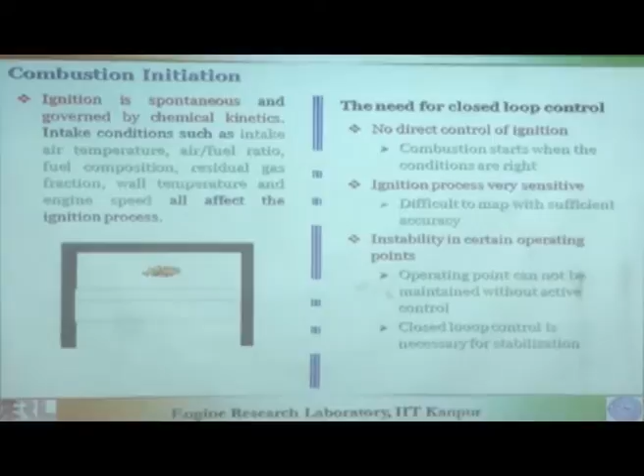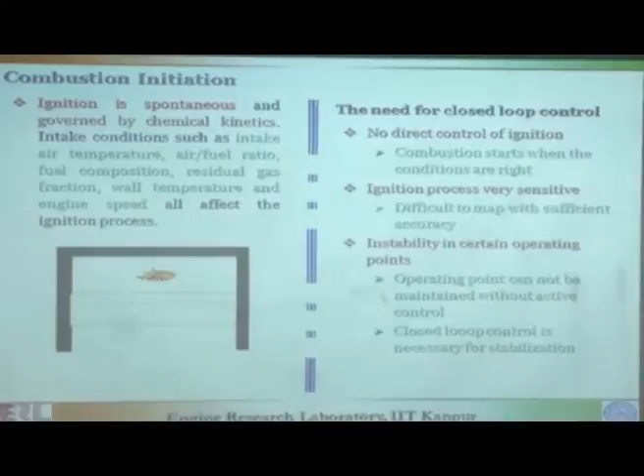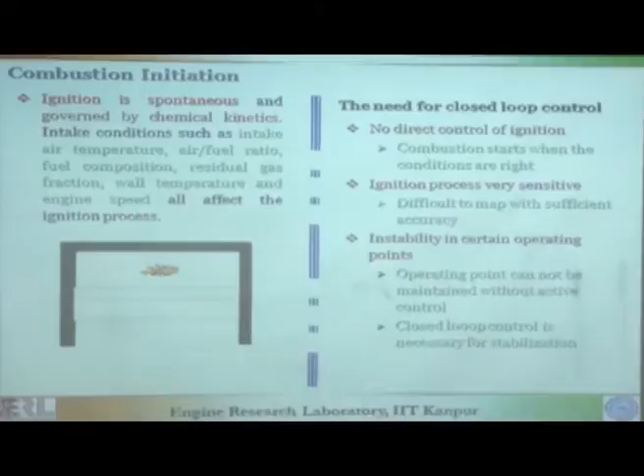Okay. So there is a need for closed loop control. You cannot just take some action and then wait for it to happen. It is always better to have closed loop control. Closed loop control is required because there is no direct control of the ignition. Combustion starts when the conditions are just right. The ignition process is very sensitive: if one parameter varies, it will change; if two parameters vary, you never know. So it's difficult to map with sufficient accuracy, and that's why closed loop control is essential.